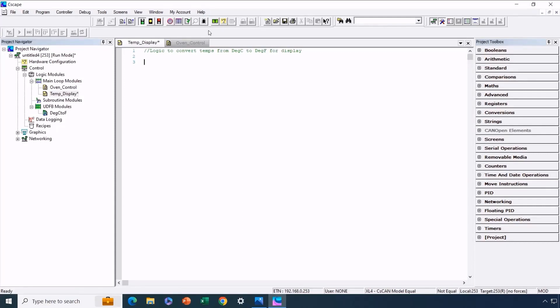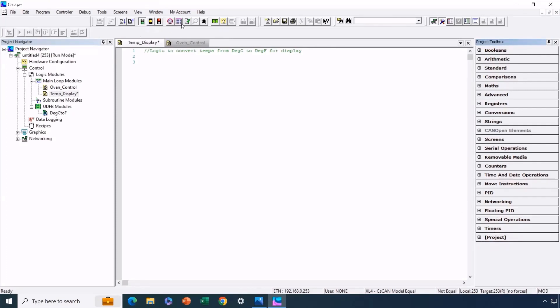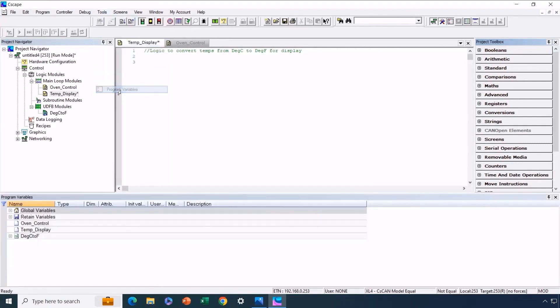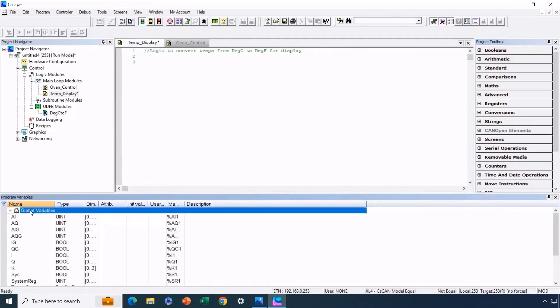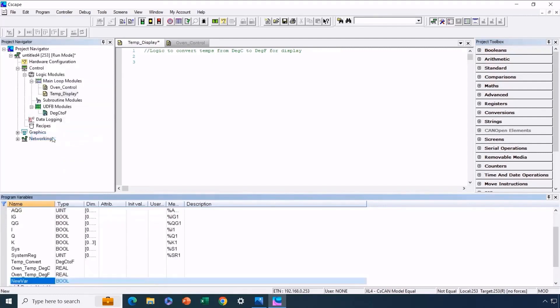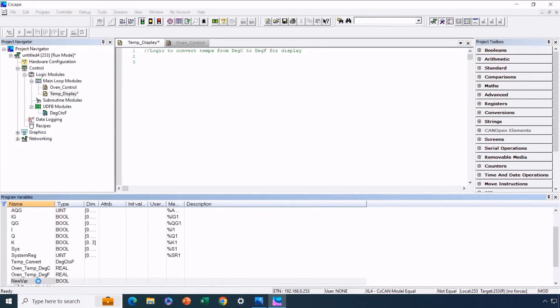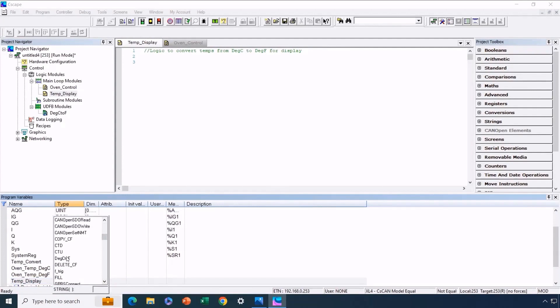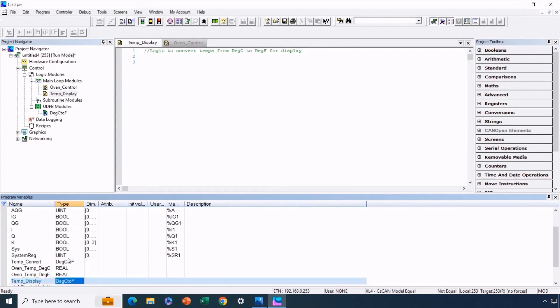Instead, we'll need to declare an instance of the UDFB. While it's technically possible to drag and rename it later, we prefer a more organized approach. We'll access the variable window and create a new variable there. Navigating to the global variables area, we'll right-click and select Add Variable. This instance is specific to this section of the program, so we'll name it TempDisplay. We'll assign the appropriate data type, which is degree C to F, which corresponds to the user-defined function block type.